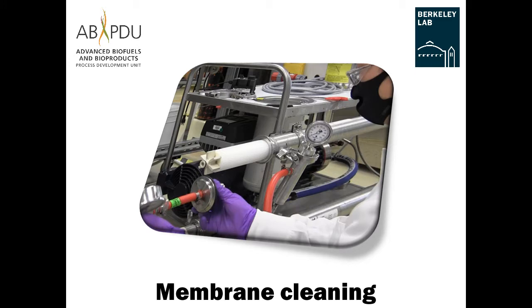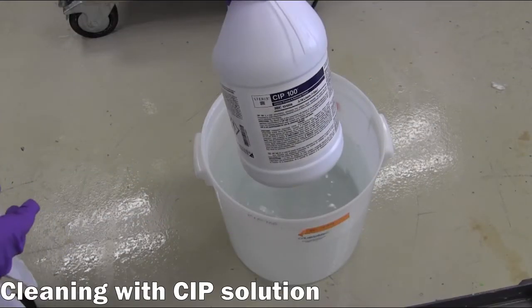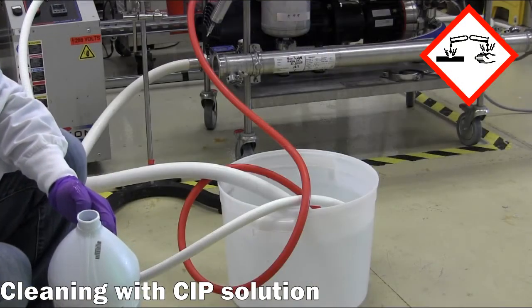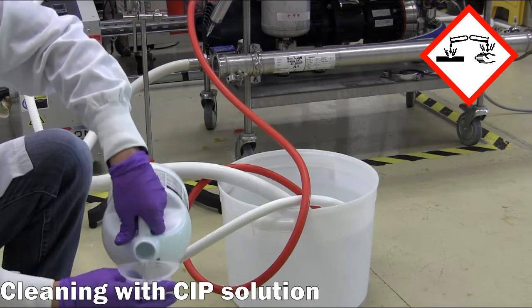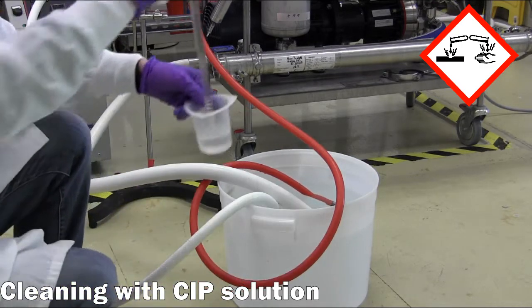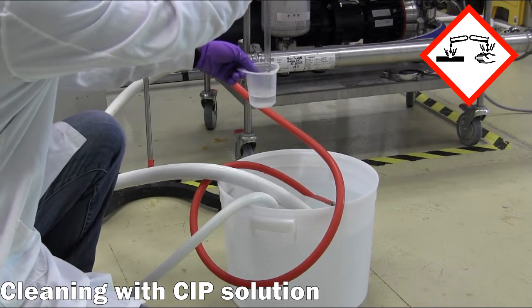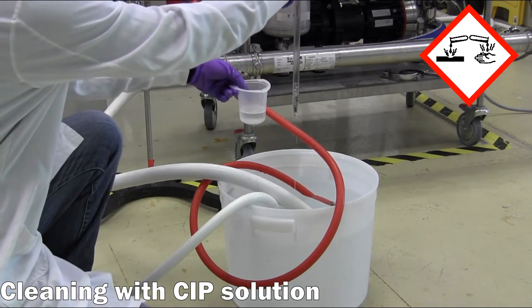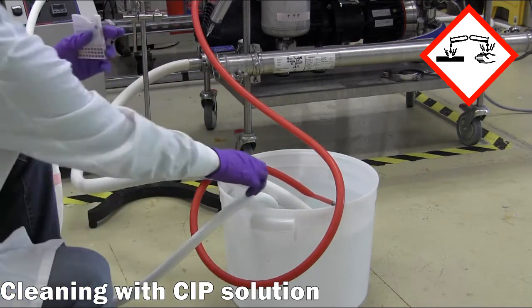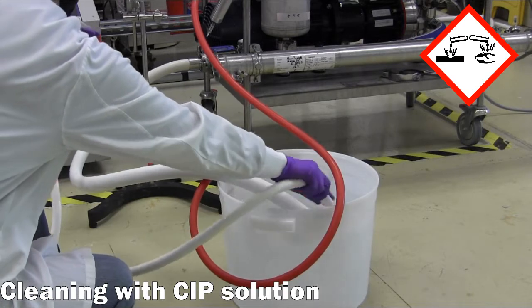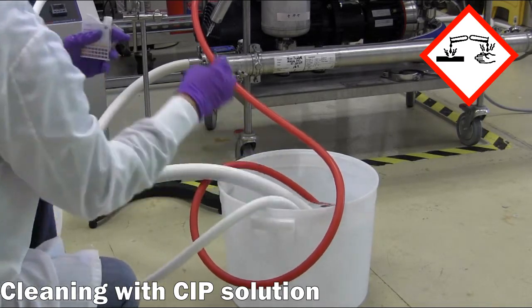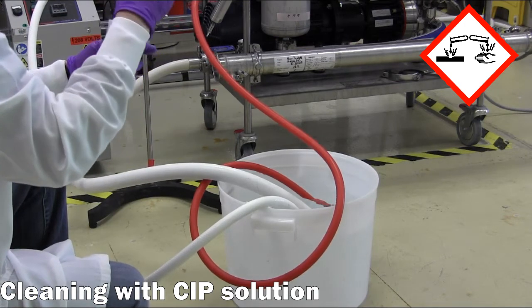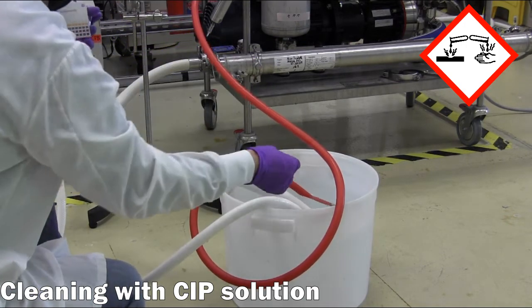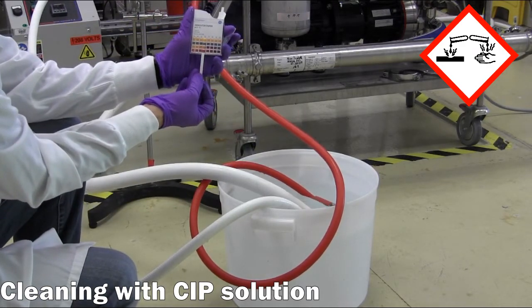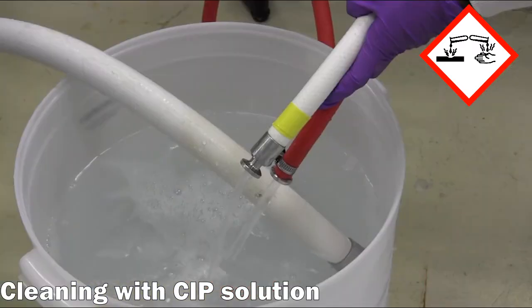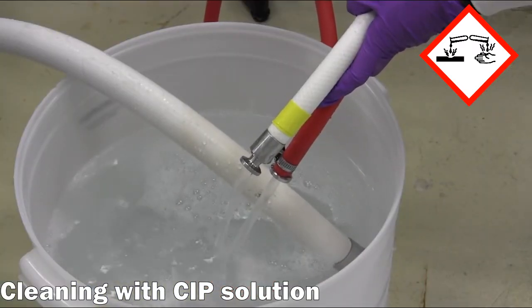Membrane cleaning. Membranes may be coated with a layer of glycerin or other storage solution and must be thoroughly cleaned before introducing process material. First, a high pH cleaning solution is made up by adding a small amount of CIP 100 to the water. Be mindful of the hazards of working with caustic solutions. A pH test strip can be used to verify that the pH is around 11. Now, the solution can be recirculated for 30 minutes.